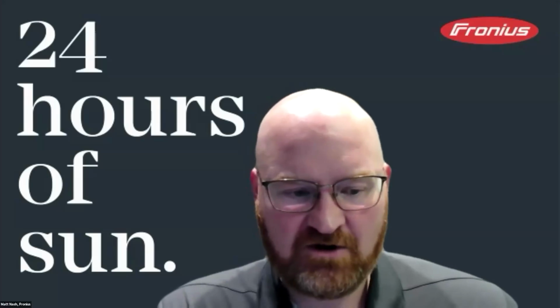Also, another thing to note is the actual weight of the inverter. The small power class weighs about 37 pounds, where the previous generation weighed about 45 pounds. For the smaller classes. The larger power classes weigh 45 pounds, where the previous generation for that 10 kilowatt inverter weighed 80 pounds. So just not having to worry about throwing your back out by picking it up, because it really was a team lift thing with the last generation, where it's not so much anymore. Those are the key features that make it a whole lot easier to install in comparison to our previous generation.